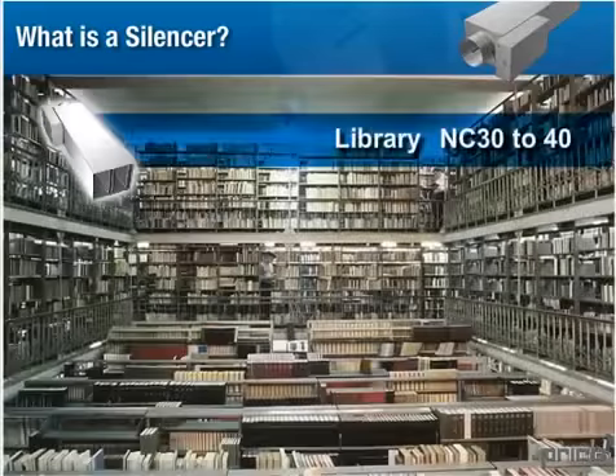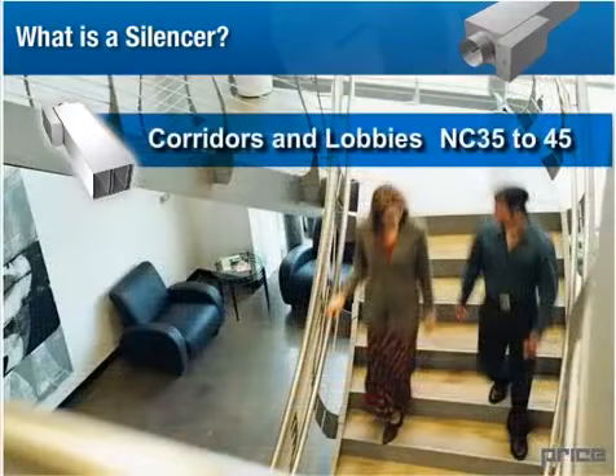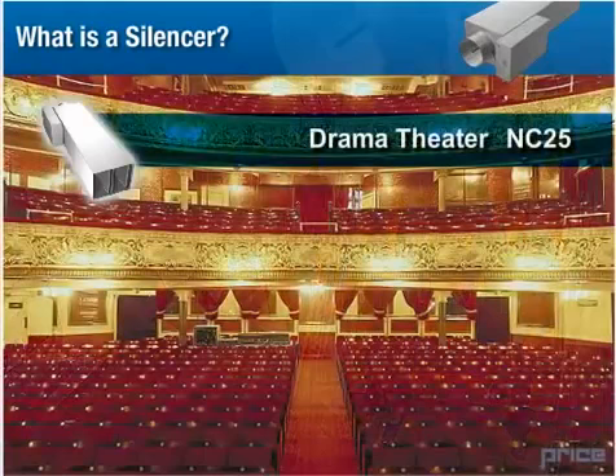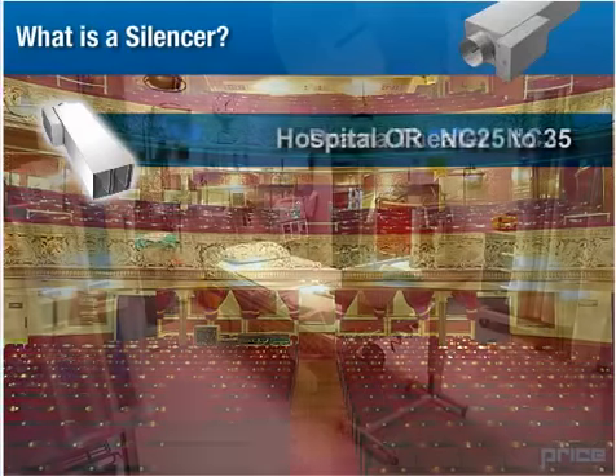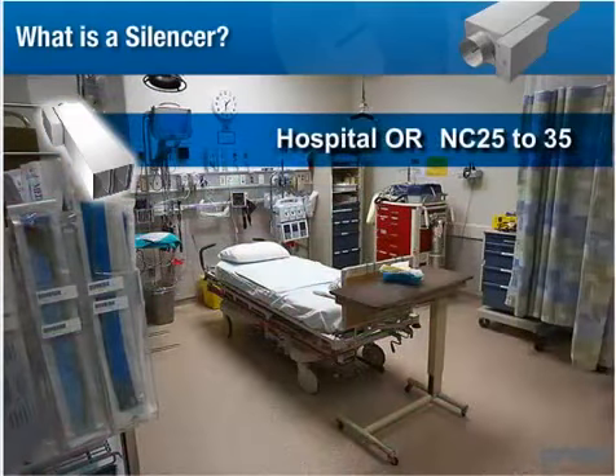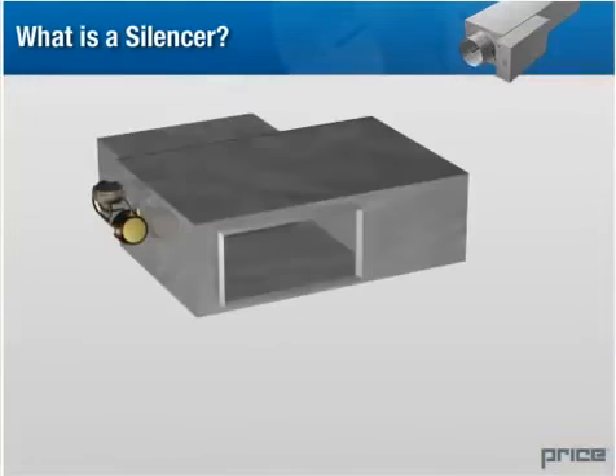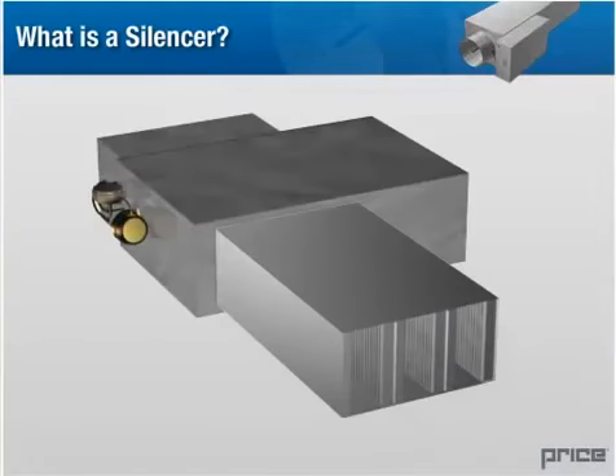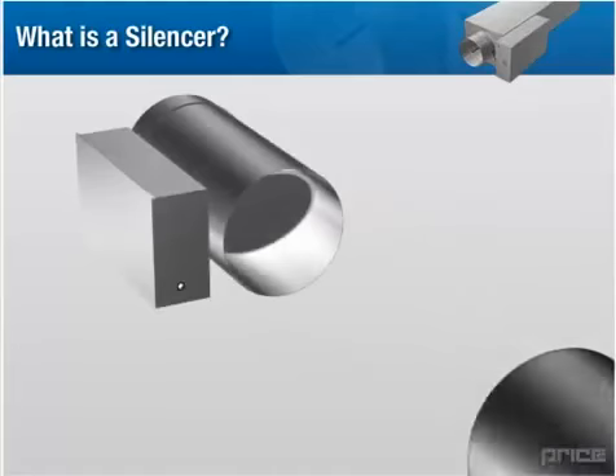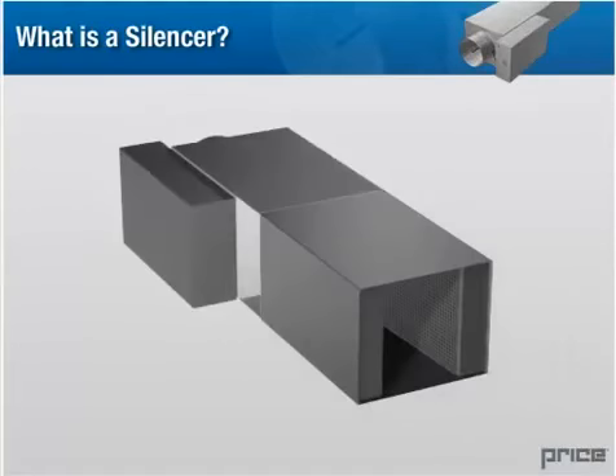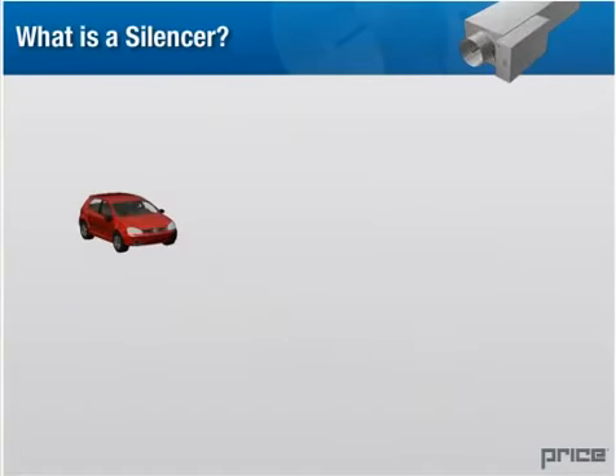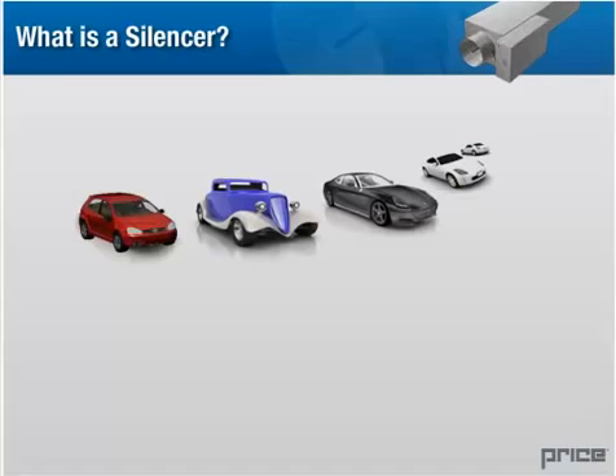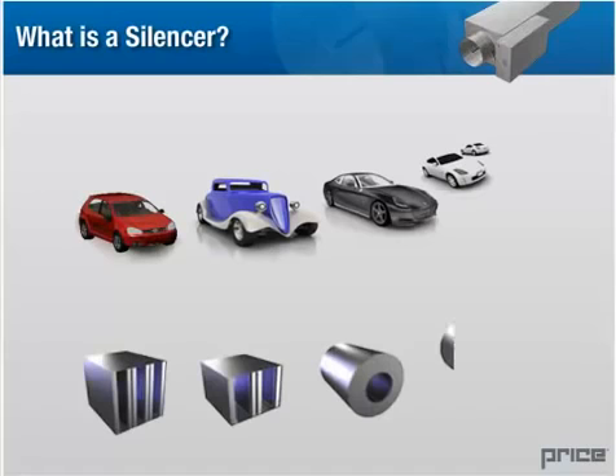It's important to attain proper NC values in areas where you are installing terminal units. If a desired NC level cannot be met with a standard terminal unit, the addition of a silencer can assist in the reduction of the NC rating. The challenge is applying the proper silencer to the proper terminal unit to obtain optimal noise reduction in the desired area. Just like there are different types of mufflers for different types of vehicles, the same applies to selecting the right silencer to fit your terminal unit.